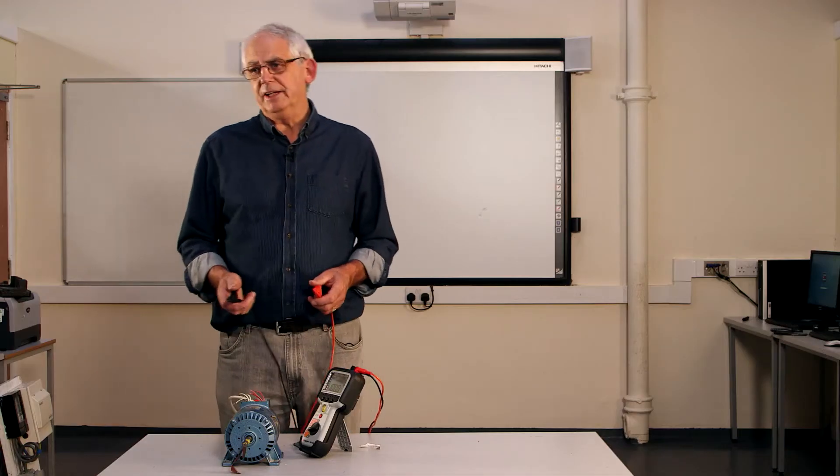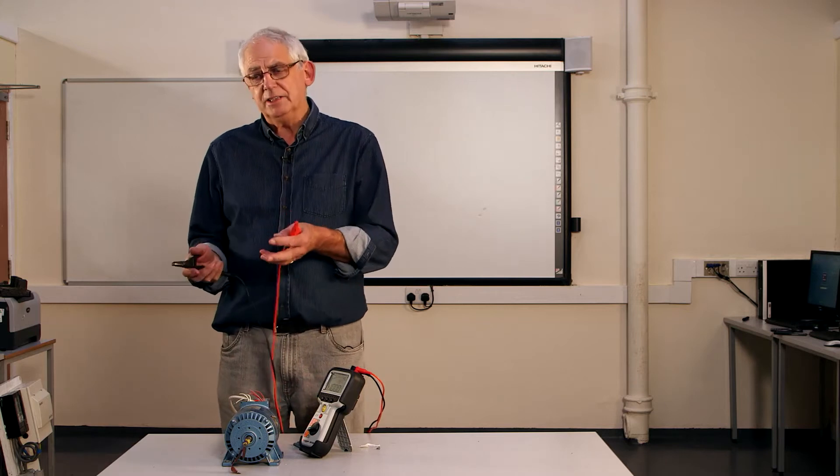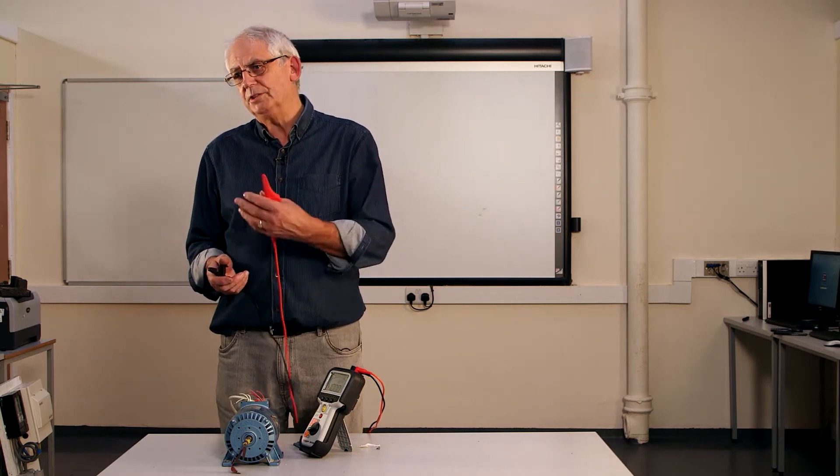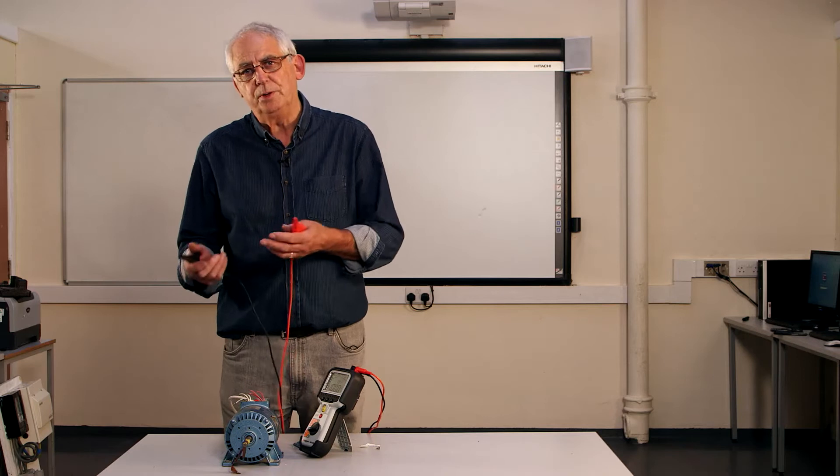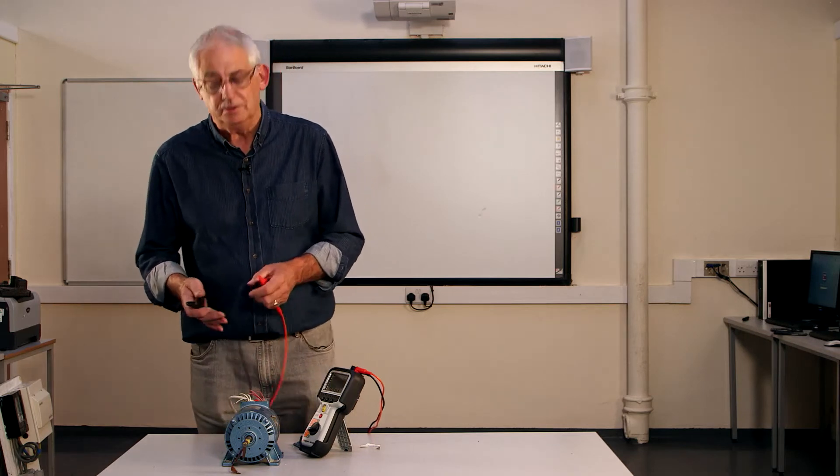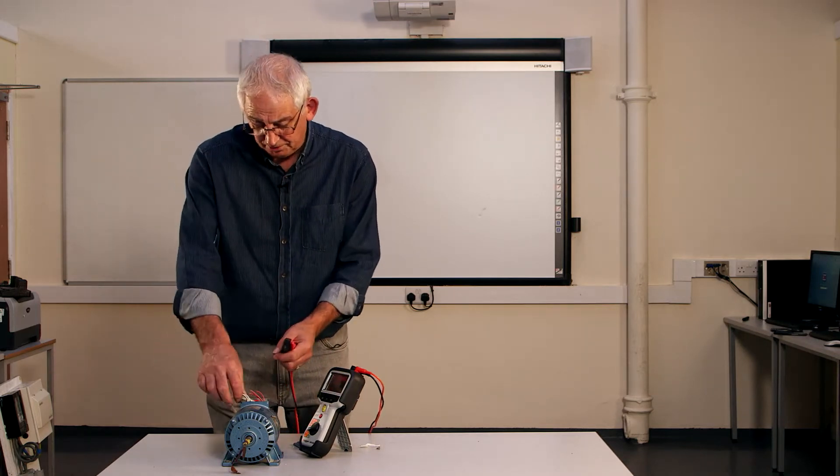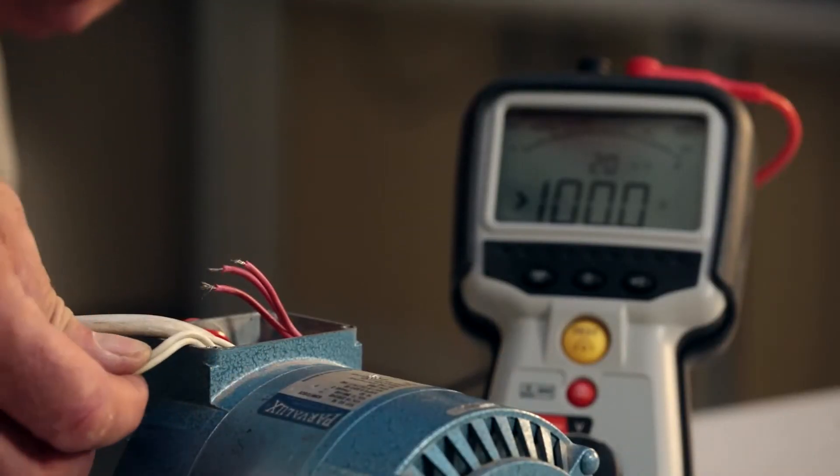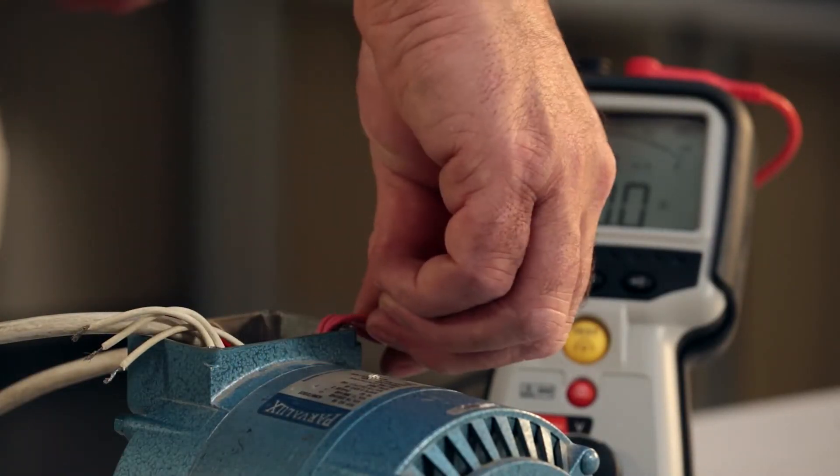Having zeroed the leads, I now need to identify the ends of the windings and make sure that each of the windings has got pretty much the same resistance value. So first of all, we can obviously tell that one end of all of the windings are going to be white and one end, the other end are going to be pink.